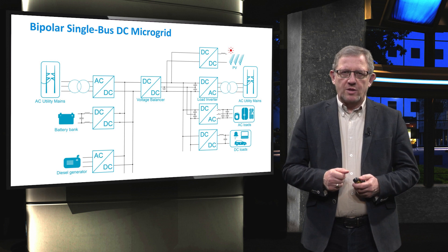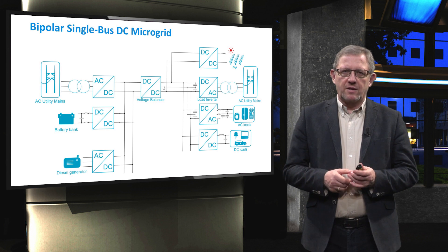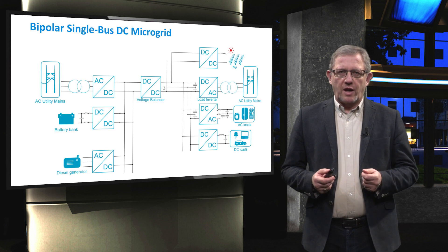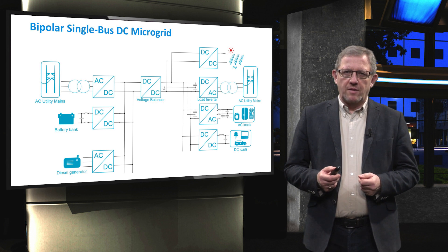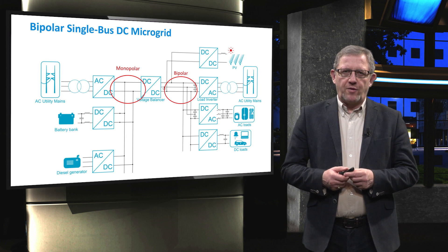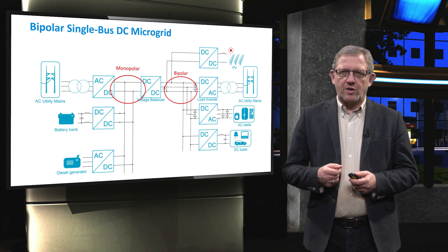The slides show a schematic diagram of a single bus bipolar DC microgrid. The bipolar connection has two low voltage conductors with opposite polarities grounded at one or both ends. If both ends are grounded, then each link can be independently operated and controlled. In the figure, one monopolar DC bus on the left is connected to a bipolar DC bus on the right.